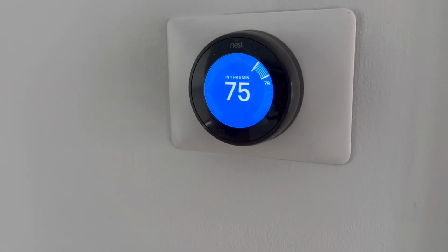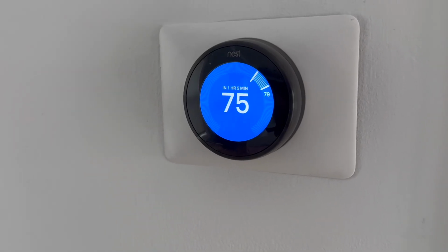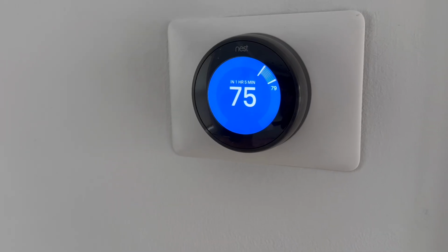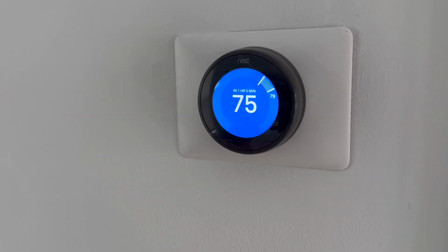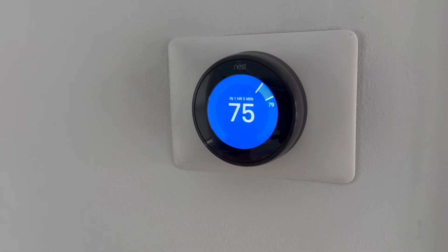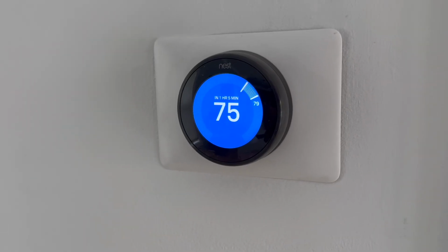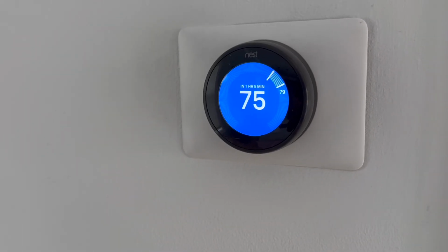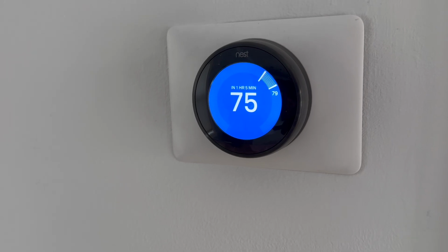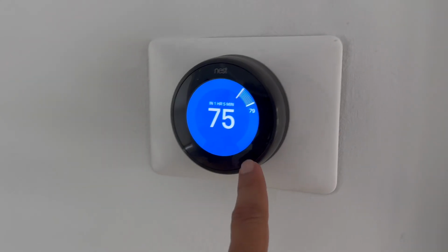Make sure the thermostat is good, then go ahead into your air conditioning system. Make sure you check that transformer to confirm it is stepping down the voltage to 28 volts. And if you don't have that 28 volts, that tells you something might be off in your circuitry or your connections to the wires coming to the thermostat.